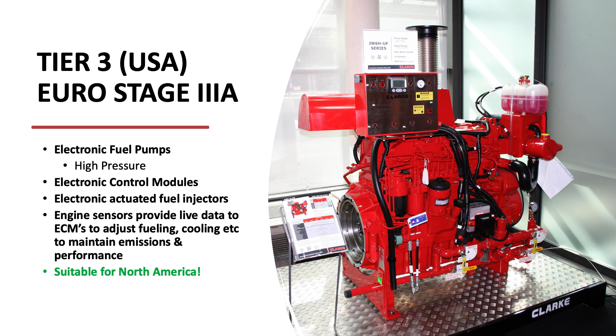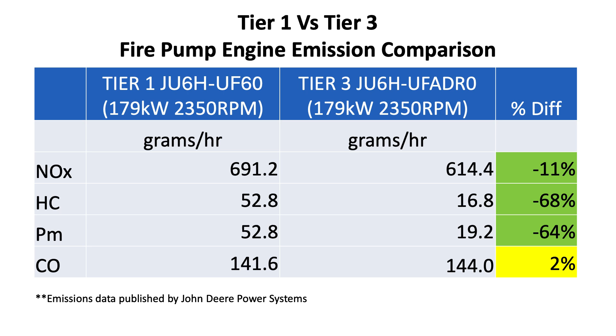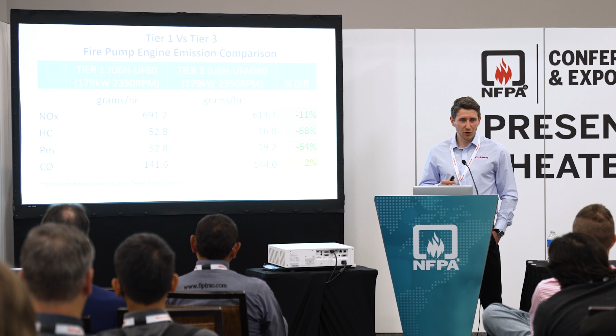This table compares those two different engine platforms, from the Tier 1 NSPS engine to an equivalent power Tier 3 engine. Both use a John Deere base engine, and you'll see on the right there are quite significant reductions in unburnt hydrocarbons and particulate matter. Carbon monoxide shows negligible change, mainly because at Tier 3 level for fire protection, we don't want to go above that — going higher, to technology used in on-road applications, means using things like diesel particulate filters and selective catalytic reduction, and that technology can actually reduce engine reliability, which is something we don't want for fire pumps. When the engine's called upon, we want to ensure it's going to start.